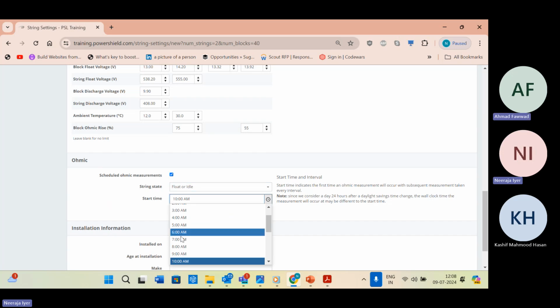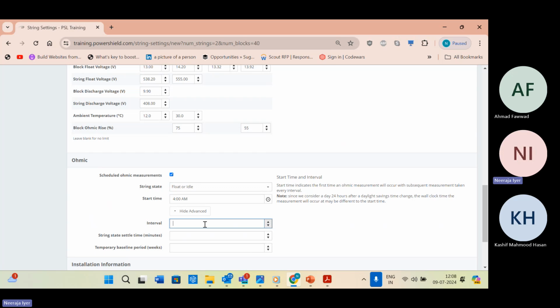You can set the time you want every day, say at 4 a.m. And you can also set the interval, say 60 minutes. No, this is the string settle state. The interval is a minimum of 1 day, 24 hours. As you can see, we consider a day as 24 hours. So the interval is how many days you want to do impedance within. The minimum is 1 day, so we are giving 1 day.